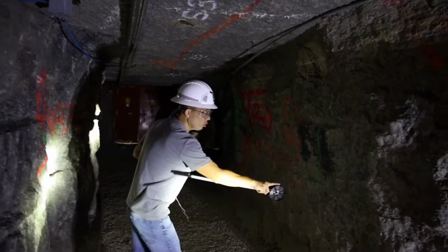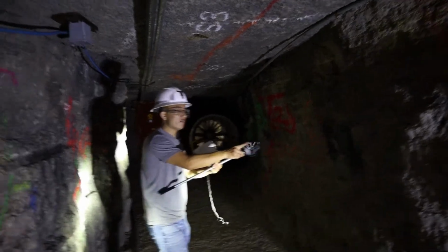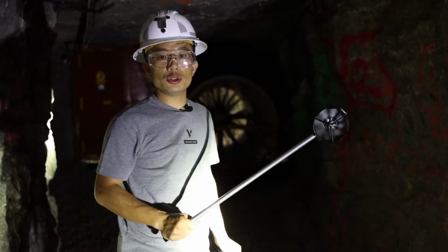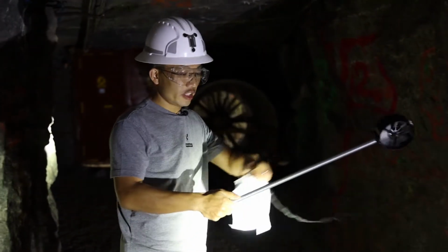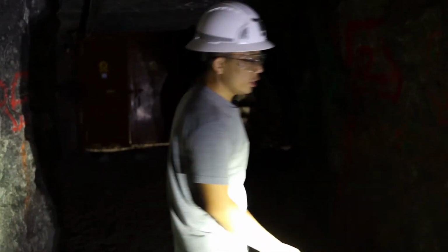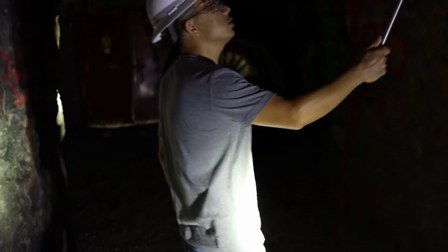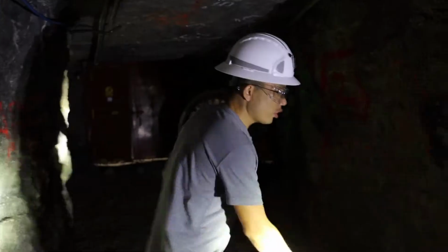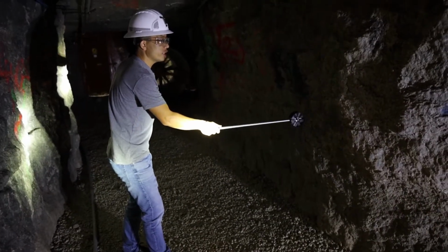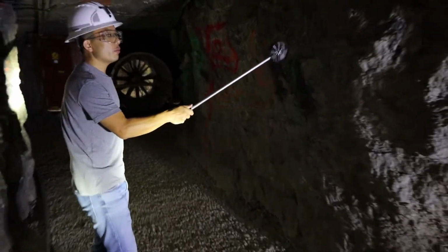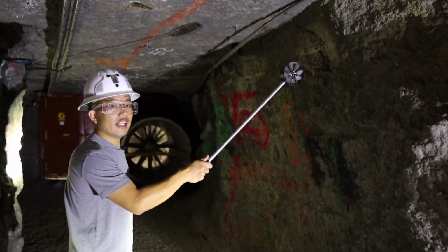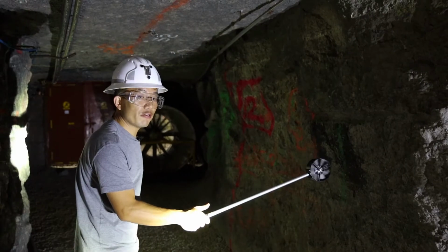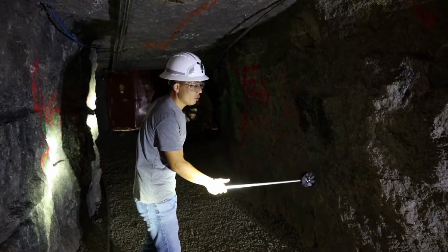Normally, we don't hold this and move it up and down. We have to use this extension rod. Also use a proper length of the extension rod so you can reach the bottom and the top of the airway as much as possible. The speed of the traverse has to be slow, normally at a speed of less than 0.2 meters per second. So that is about 5 seconds per meter.